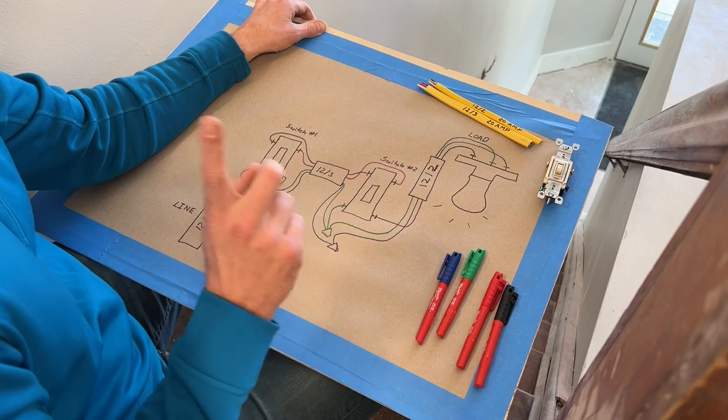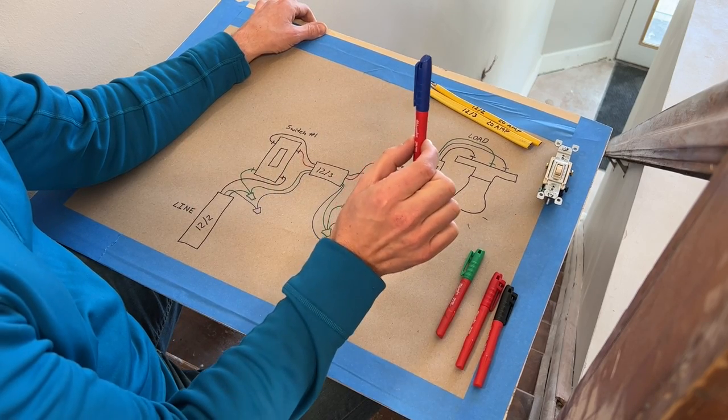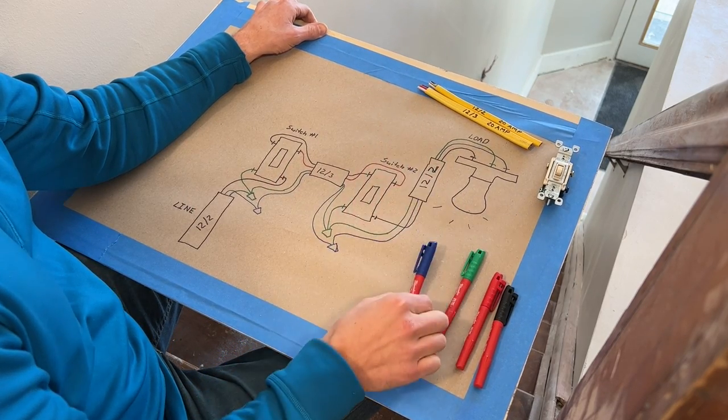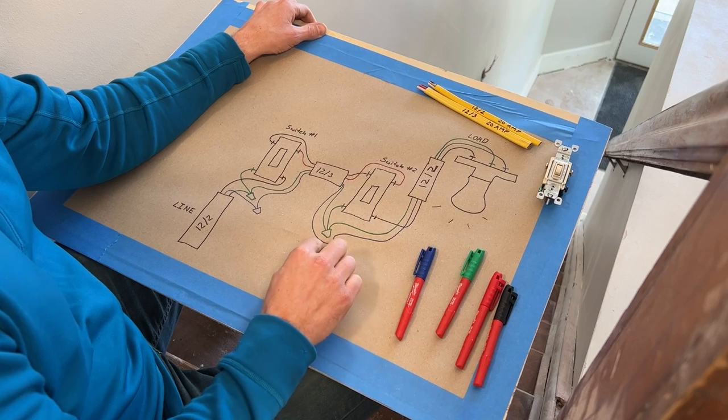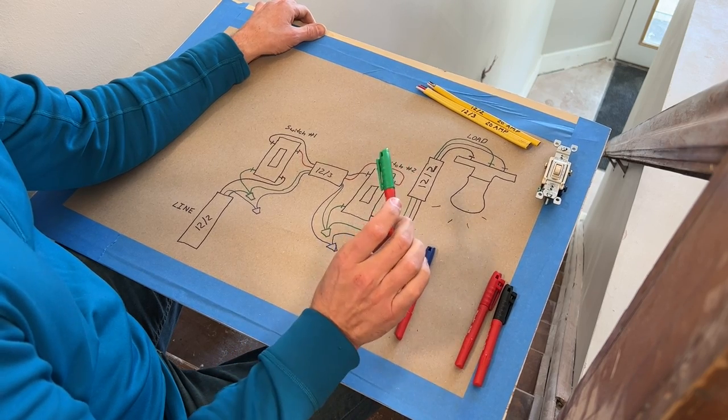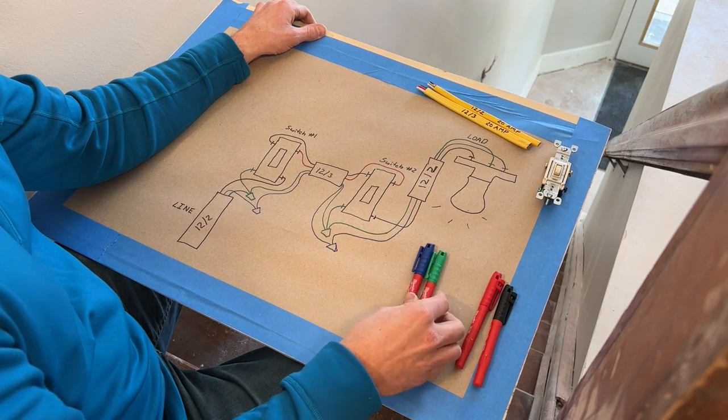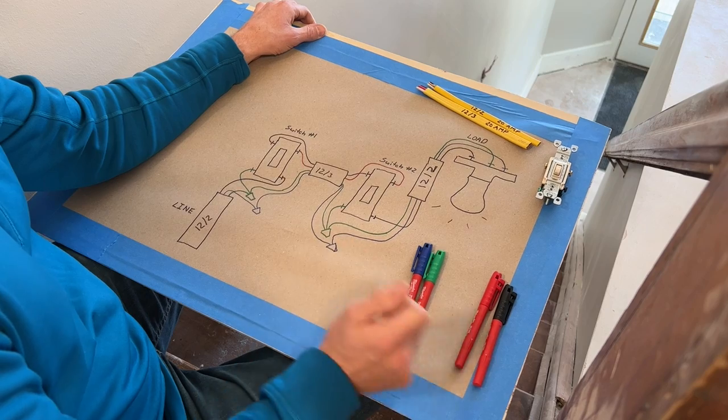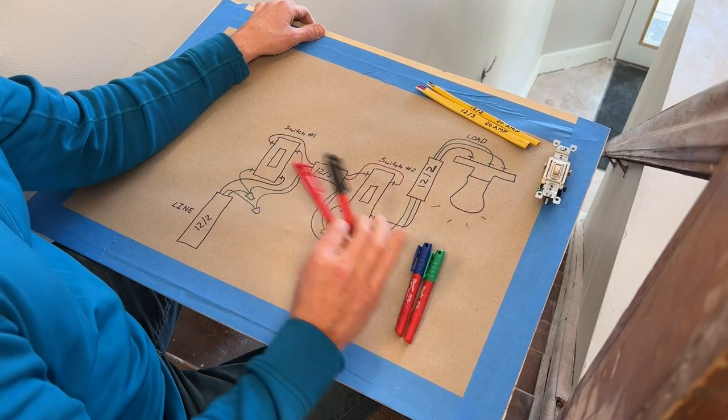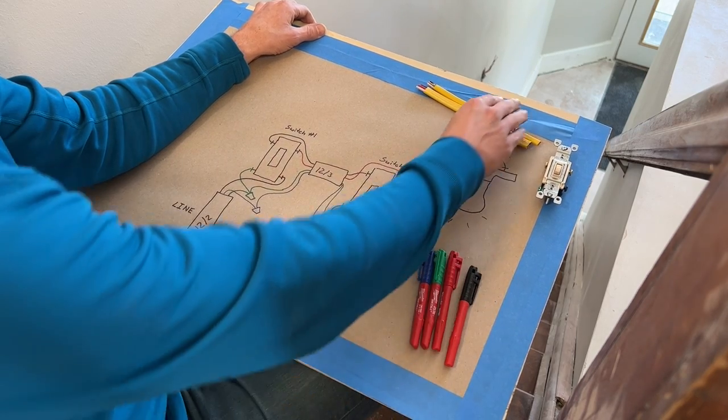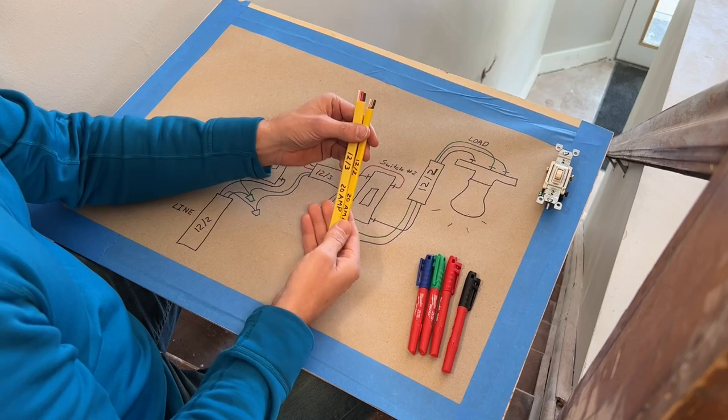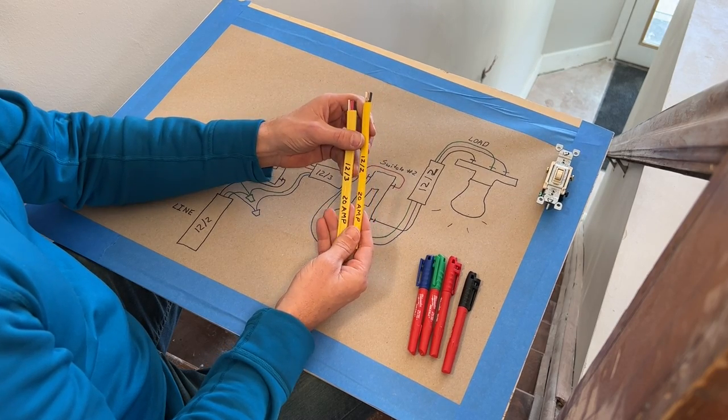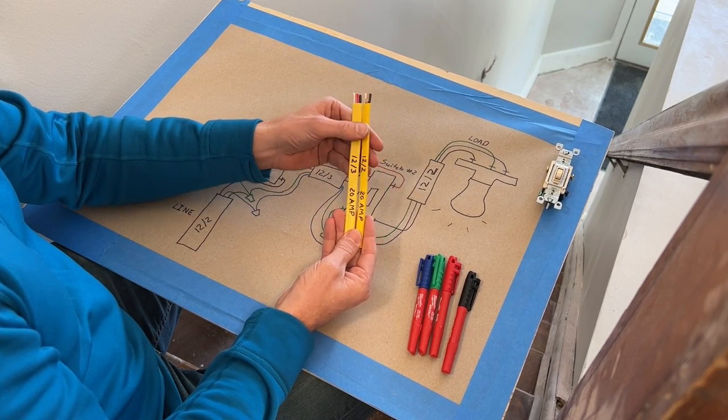A few callouts here that might be confusing. The most confusing is blue actually would indicate a white wire, which is neutral. Green is ground - that's a little bit more self-explanatory, even though it'd be a bare copper wire. And then black and red are true to what you should see if you're using standard Romex, like a 12-2 Romex here and a 12-3 Romex.